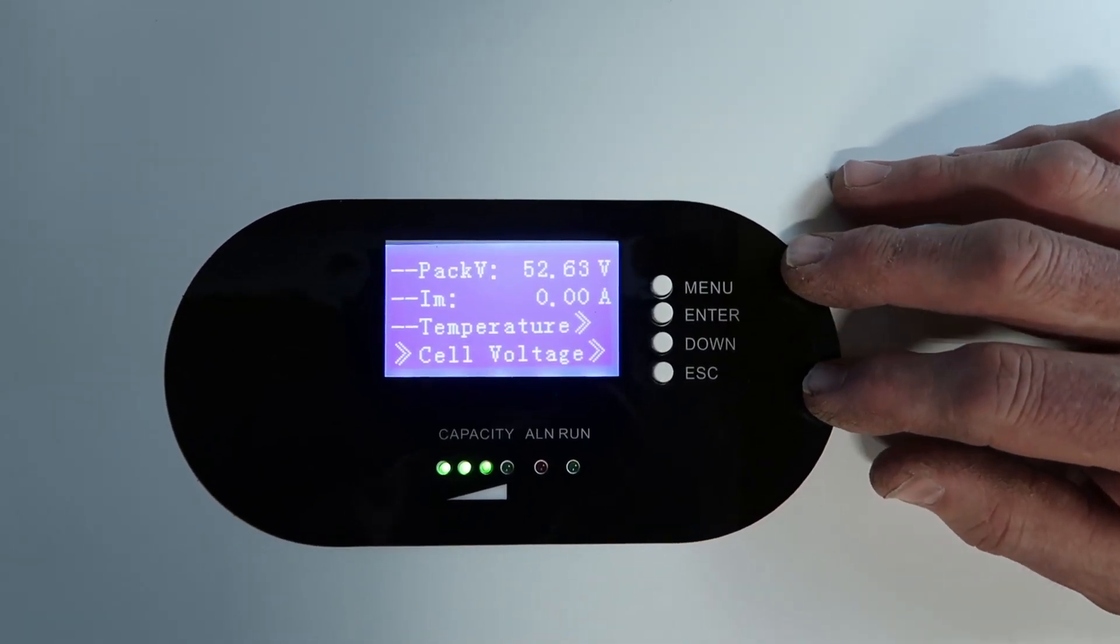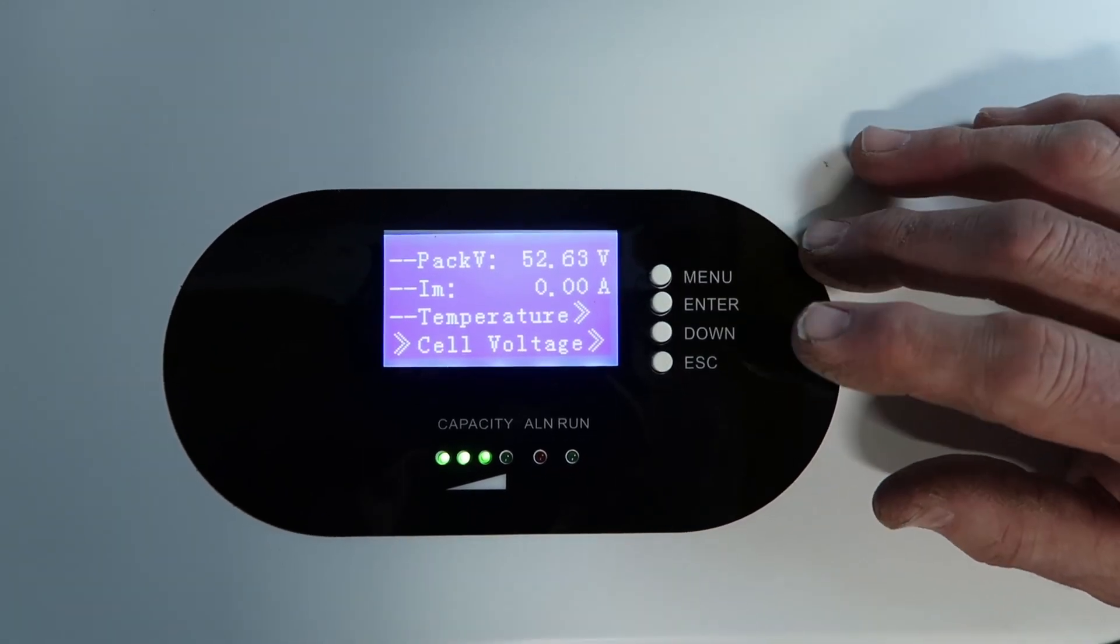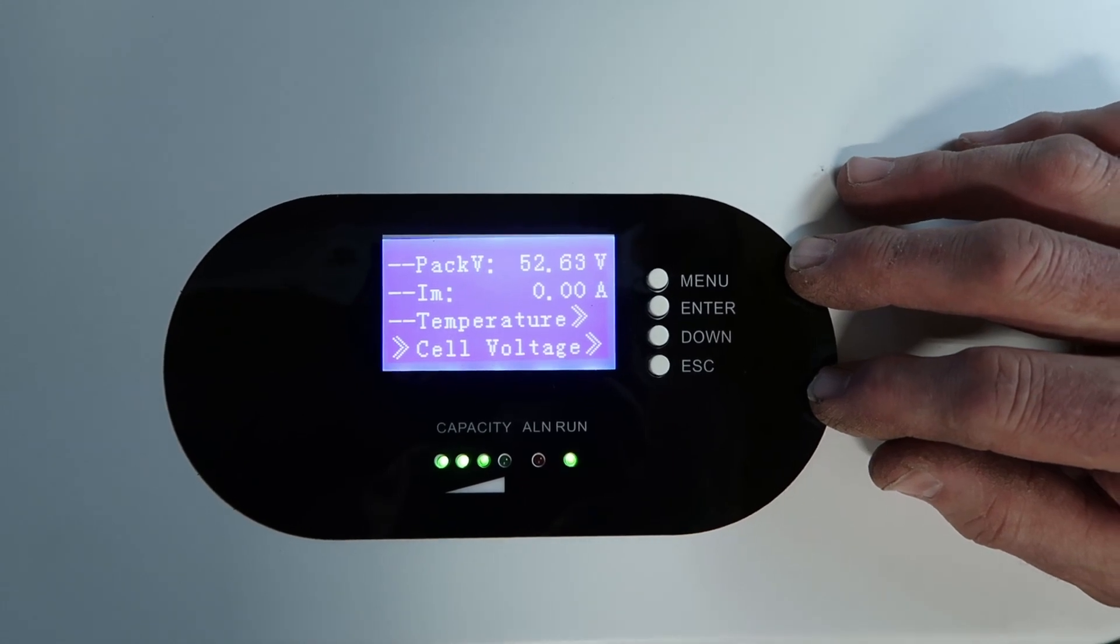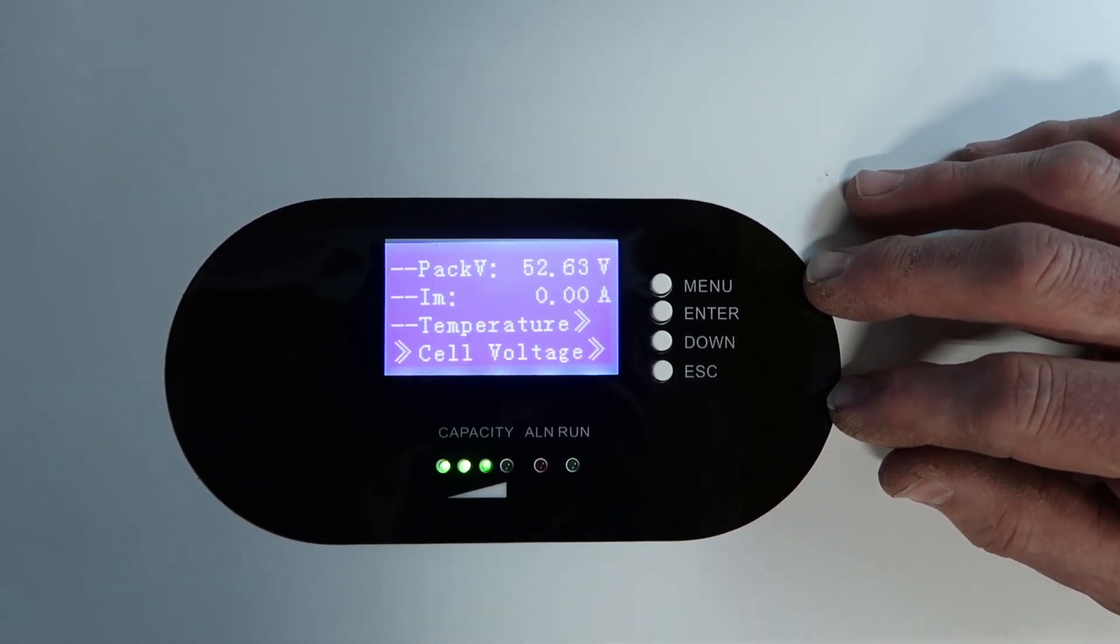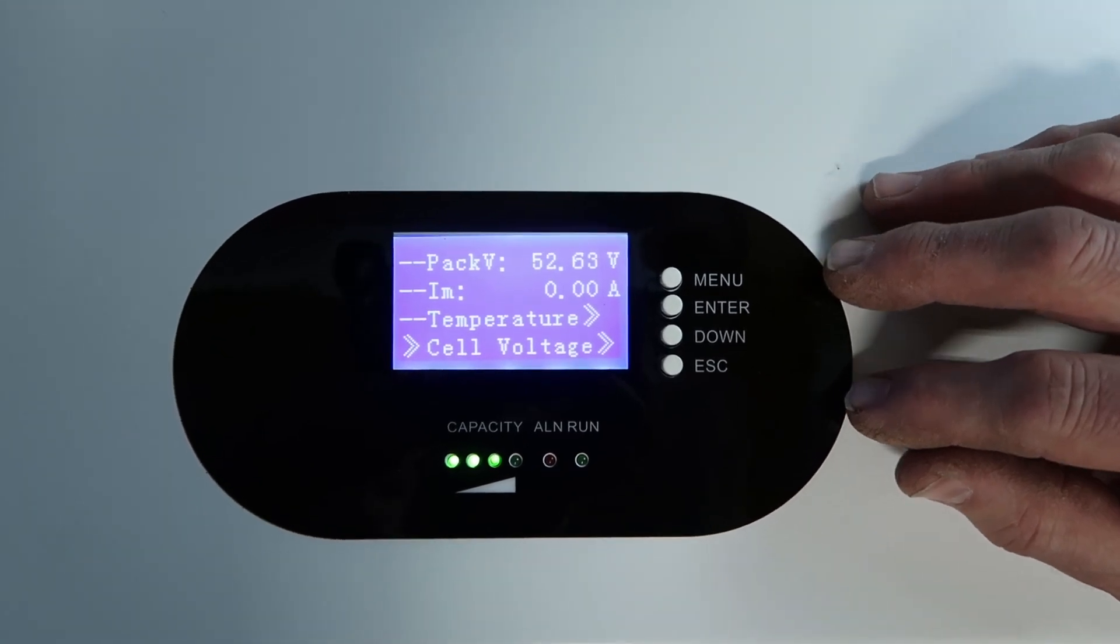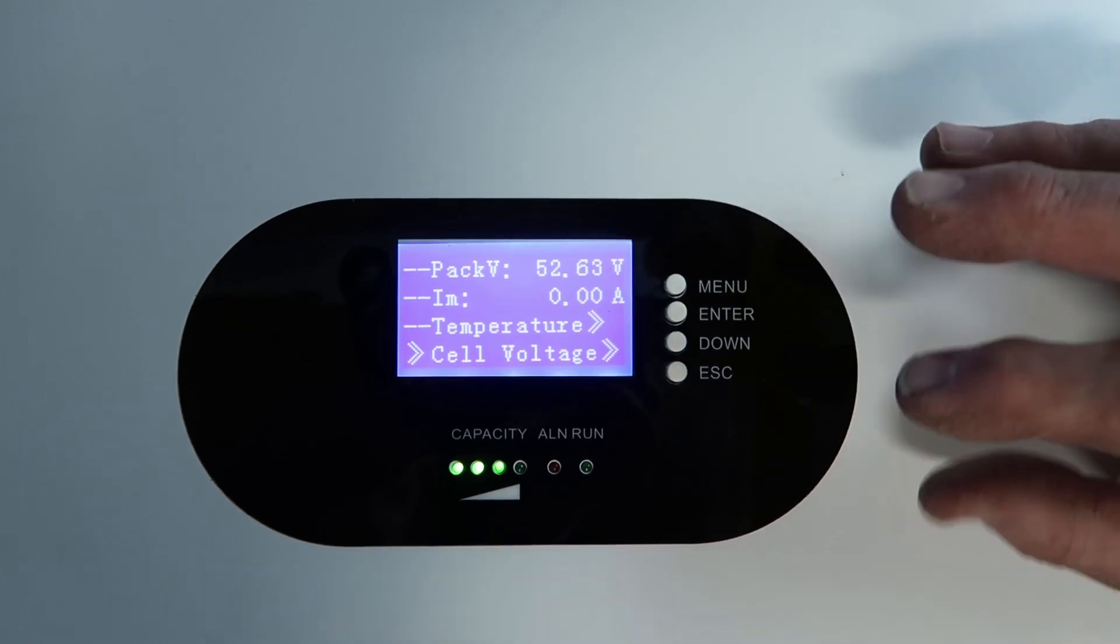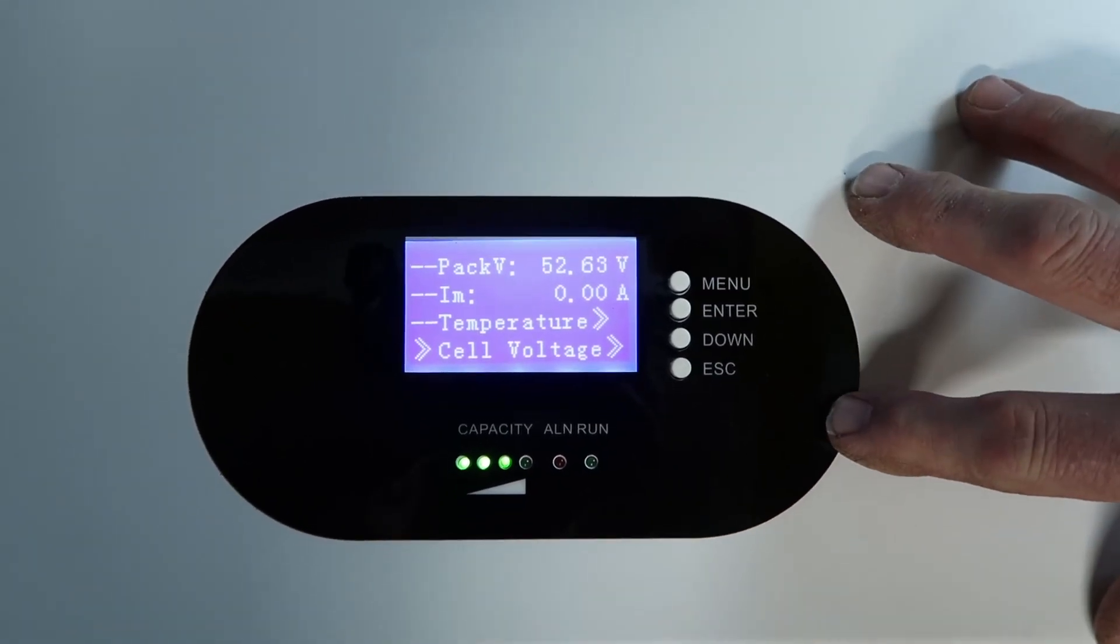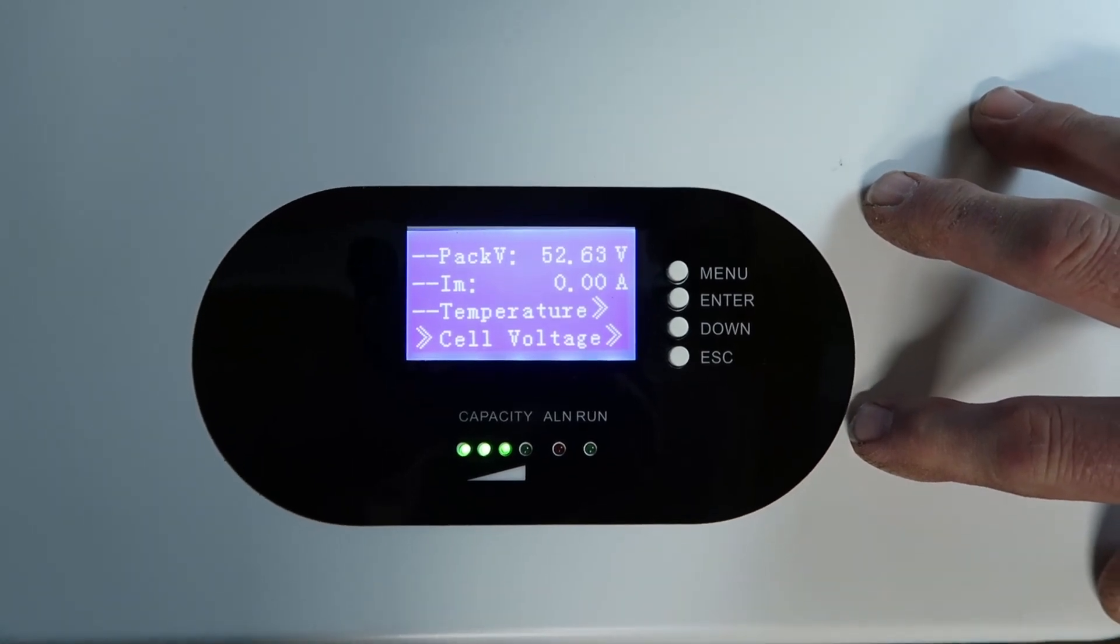It's very interesting because you can see the cell imbalance. We have two of these hooked up and running. We did get initially about a 300 millivolt differential in the different cells, but it's balancing and coming down. So I think we're down to about 270 millivolt difference over a few cycles.